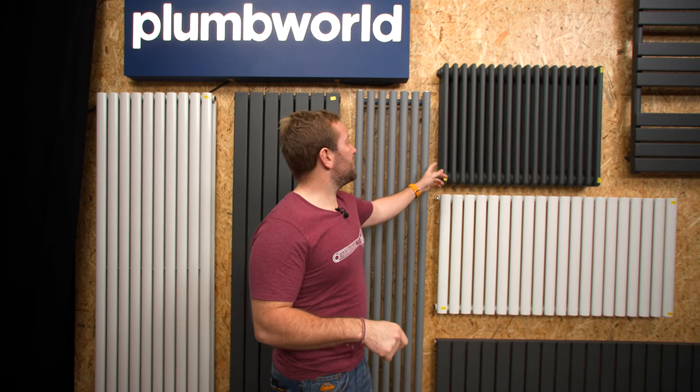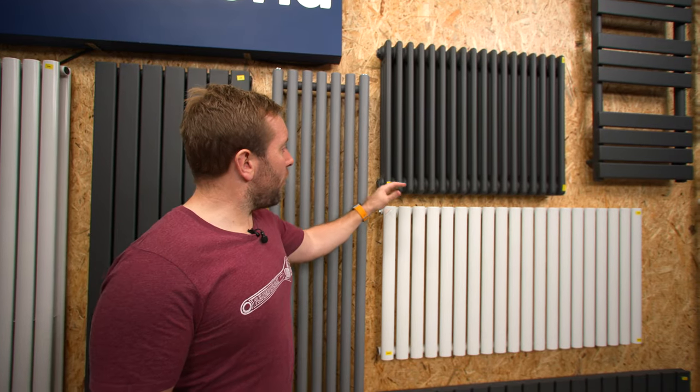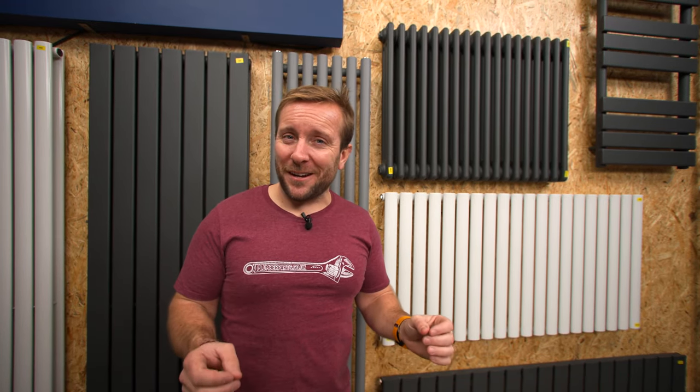Material is really, really important when it comes to how you're going to fit the radiator on a wall, what wall you're going to fit it to, but also how quickly that radiator heats up and cools down — we call that the heat curve. For instance, big thick steel radiators like this beast here will have what we call a slow heat curve. As we introduce hot water into it, because it's got so much material to heat up and cool down, it takes longer to start feeling really hot. Once the heating's gone off, it also takes a lot longer to cool down. If I was working in an old cottage, or if it was just plasterboard fixings, I would probably look into buying feet for these — little stabilising feet on the bottom to take the majority of the weight, and then pin them at the top.